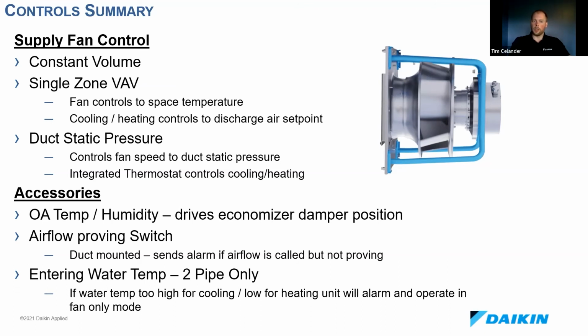It will always control to that integrated thermostat set point from the room temp sensor. In single zone VAV operation, you speed up and slow down your fan to hit the space temperature set point while you're controlling the modulation of your cooling and heating coils to a discharge air set point. So slightly more advanced, more efficient control if your fan speeds are a major energy driver.